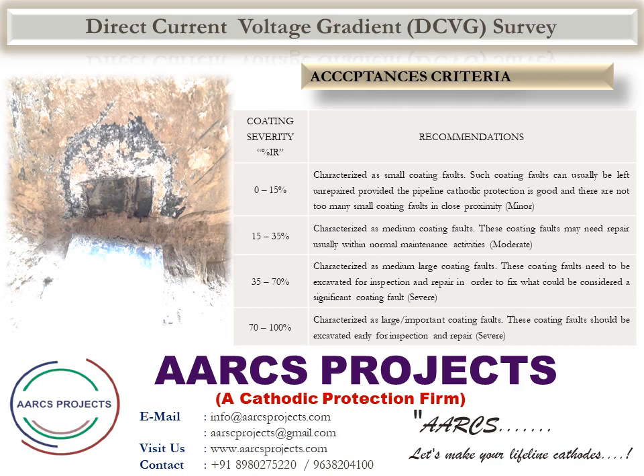Greater than 35% to 70% is characterized as medium-large coating faults — severe. These coating faults need to be excavated for inspection and repair in order to fix what could be considered a significant coating fault. Greater than 70% to 100% is characterized as large, important coating faults — severe. These coating faults should be excavated early for inspection and repair.